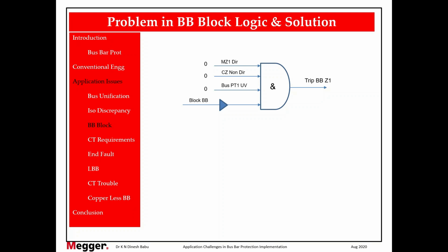That time you want to block bus bar to do some testing in the secondary. You want to take the relay secondary out of service and do some testing. That time you throw the bus bar block switch in out position. Immediately it makes a binary input high in the relay. That would be inverted and this would become 0. So when the binary input is high, bus bar is blocked. Perfect. 90% of the time it works. 10% there is a problem.